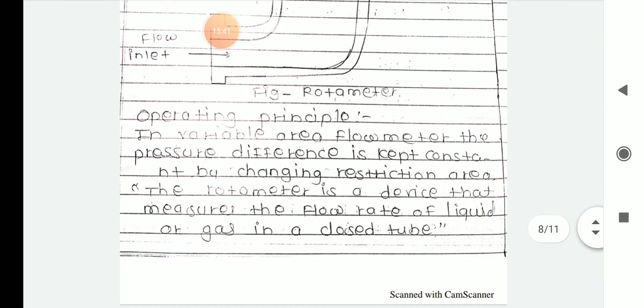Okay, so next we will discuss the rotameter. So what is that rotameter? So this is the diagrammatic representation of the rotameter, a variable area flow meter. It is one of the types of variable area meters, that is the rotameter. What is the operating principle? In a variable area flow meter, pressure difference is kept constant by changing the restriction area. You can change that area, but the pressure difference is kept constant. The rotameter is a device that measures the flow rate of a liquid or a gas in a closed tube.